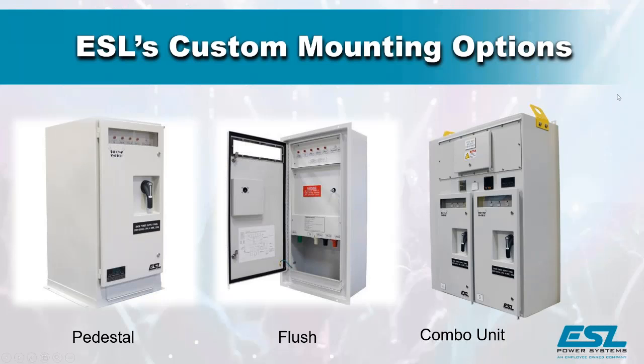I felt like there was a bit of wanting the handle to control something beyond the breaker. Currently, the handle just controls the breaker. So the whole idea is: you open the door, the unit's dead; you close the door and engage the handle, and it's live again. That's 100% how it works—there's nothing else to it really.